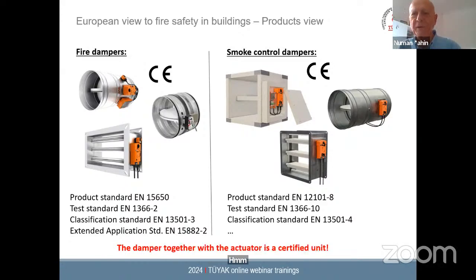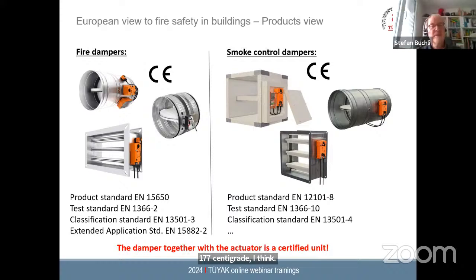Connected to this explanation, another question, for example, for the smoke dampers. In European standards, the motors are required to be in the box. But in UL, there is no regulation like this. So I think UL asks for the damper motor to resist 350 degrees Fahrenheit, 177 degrees centigrade, I think, for 30 minutes, and that is enough. Is that correct? Yeah. And here, do you still see my slide?